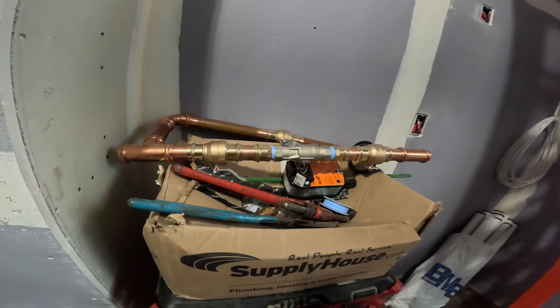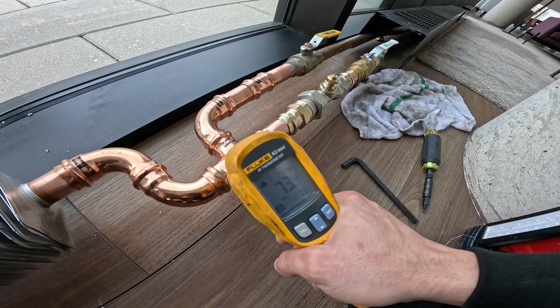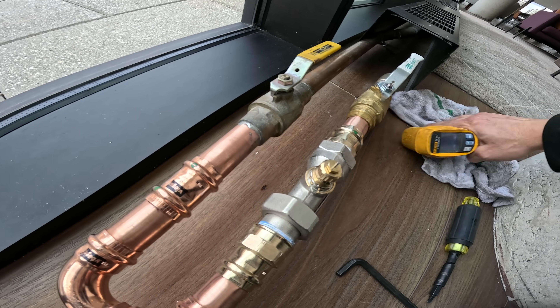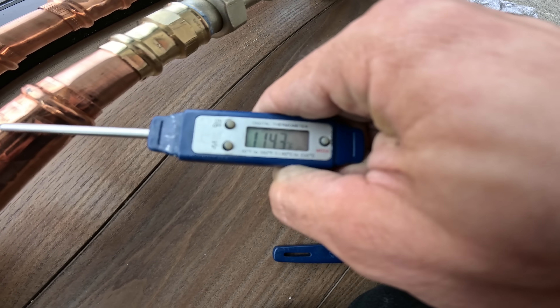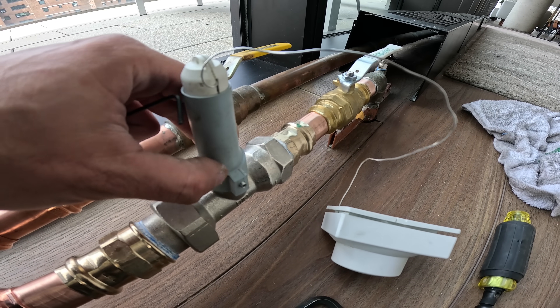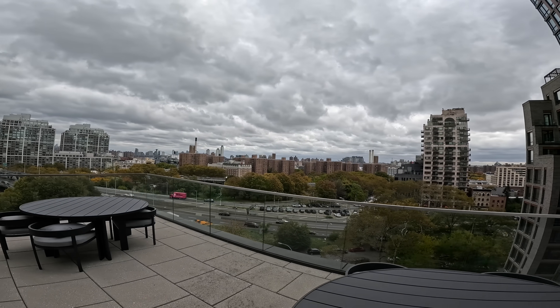We've got some more valves to open and some more press fittings here. We got heat here, but my Fluke meter stopped playing along — 69 degrees and then it quit on me. Anyway, this looks great. We got no leaks — that's awesome. Fluke is a fluke, man. We got 114 degrees in there now, so we know we got heat and there's water flowing through. This thing looks great. Let's put this controller on top, tighten it down with a little Allen key, and wrap this video up. If anyone found this video interesting or helpful, please drop a like, comment, and subscribe. New videos coming every week — catch you all next time.